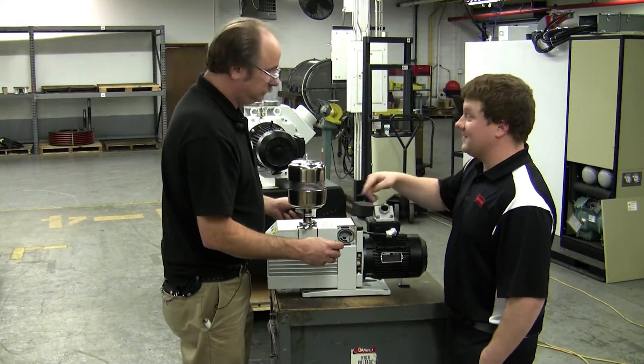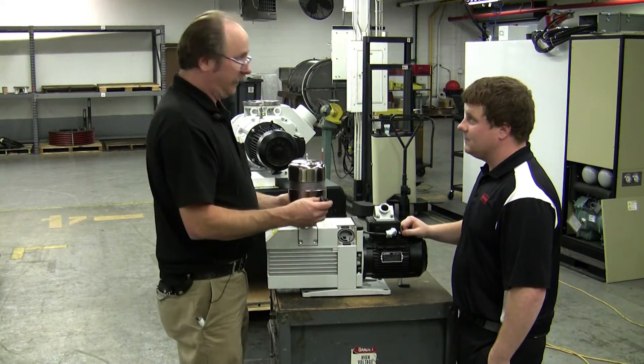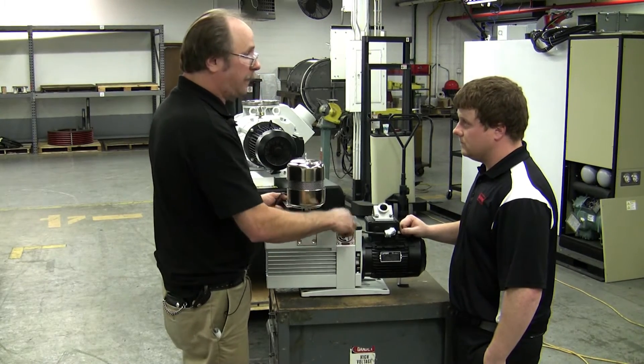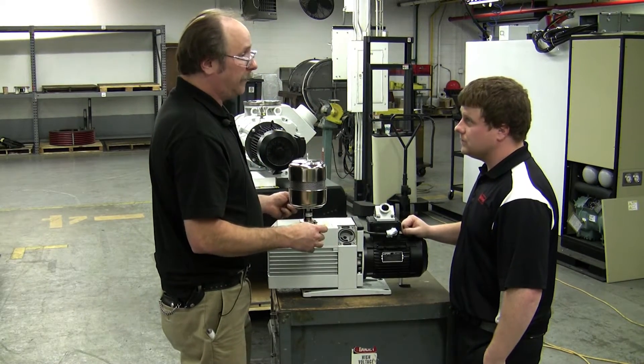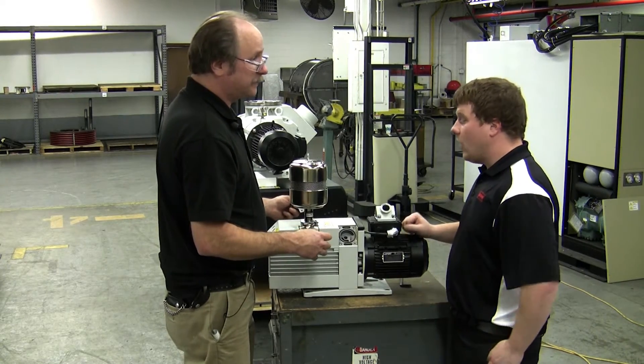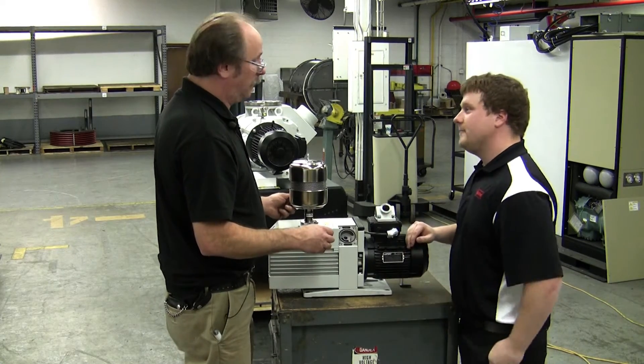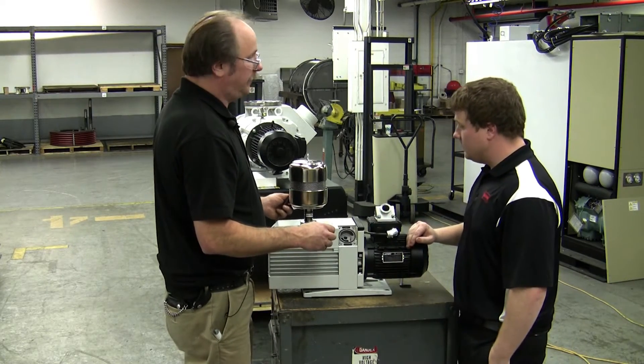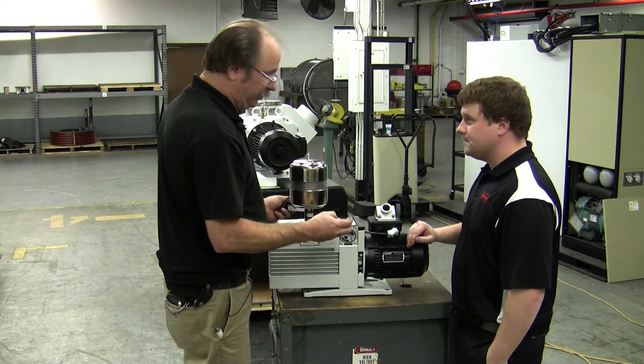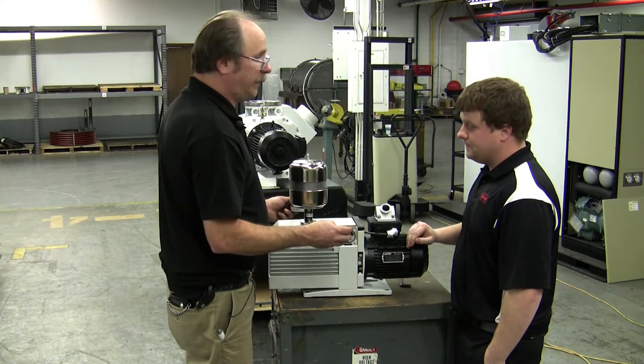So how would you know when that's starting to go bad? These are very reliable anti-suckback valves. But if you had oil migrating from the inlet of your pump out when the pump was shut off, that's telling you the anti-suckback valve is not sealing. Or if the pressure goes really high when you turn it off, the pressure should hold at a given pressure. This is a very reliable seal — you just want to make sure it's kept clean.